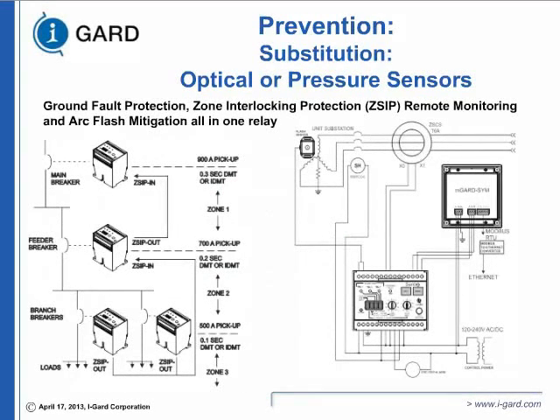You see a picture there of how it works. You basically have a zero sequence CT, as you see on your slide, that inputs to a relay. It can detect pressure also as a backup, or light, and you're cutting down the time that is required for tripping.